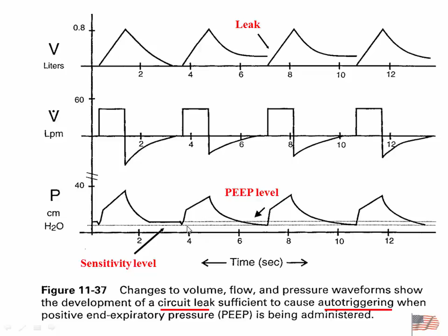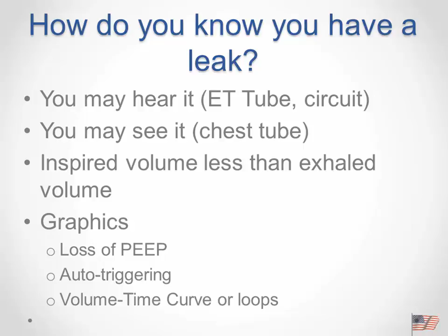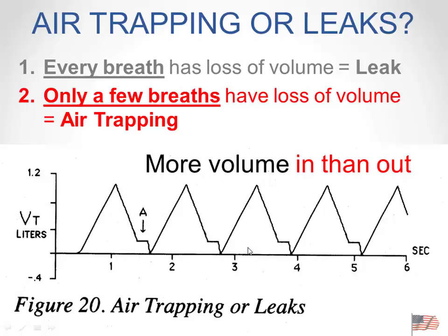And we talked about leaks. When there's a leak present, you end up having that breath triggered on prematurely. How do you know you have a leak? You can hear it. You can see it. When your volumes aren't the same, what's going in versus what's coming out. And by looking at graphics for loss of PEEP, and looking at the volume-time curve or the flow-volume or pressure-volume loops. So here I end up having this on every breath. That's a good sign that you've got a leak. If I have this just on one breath, again, it could just be auto-PEEP.